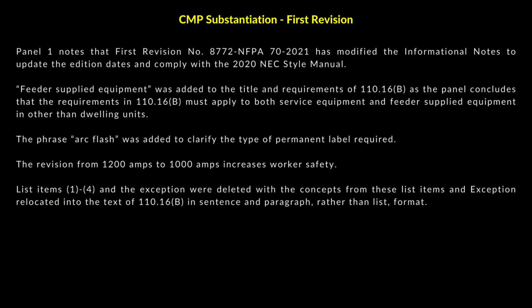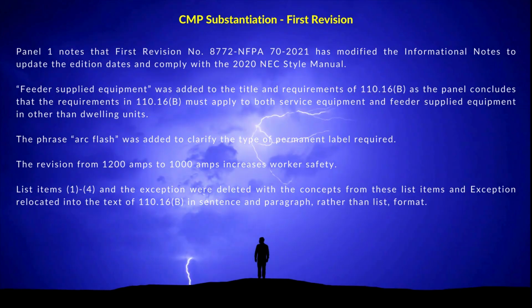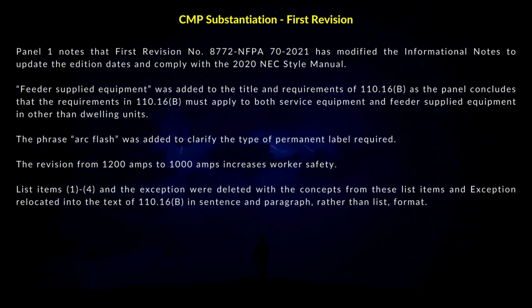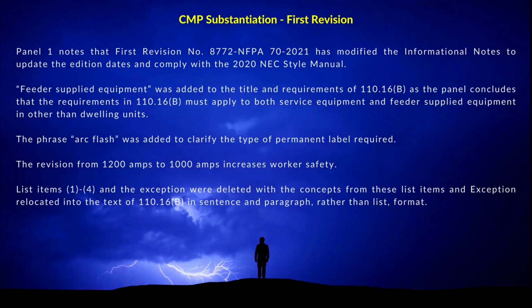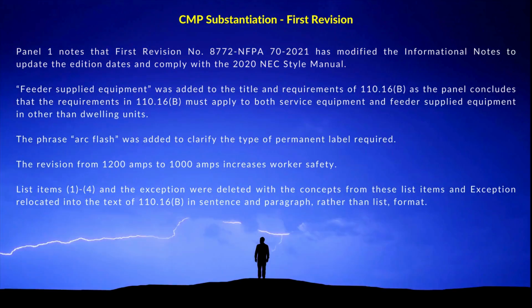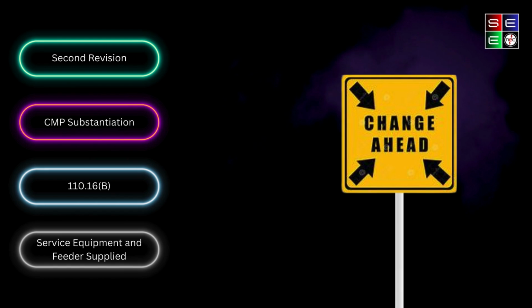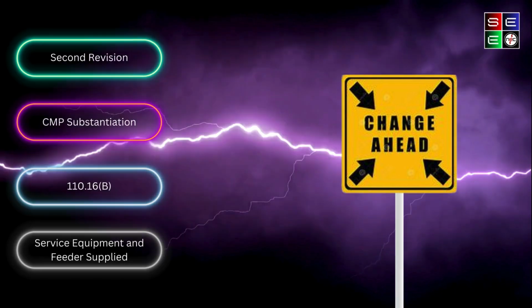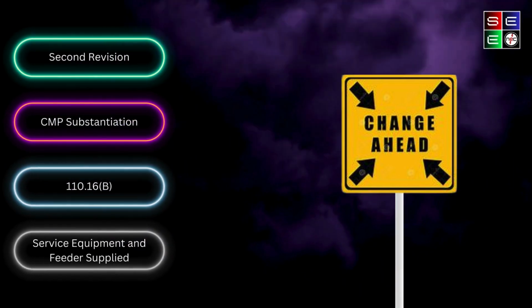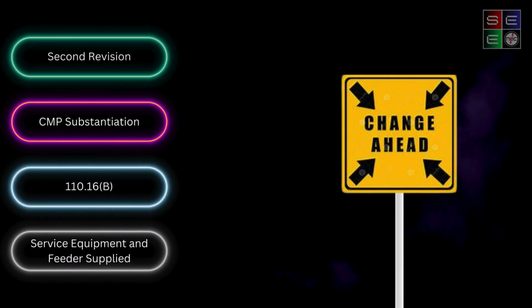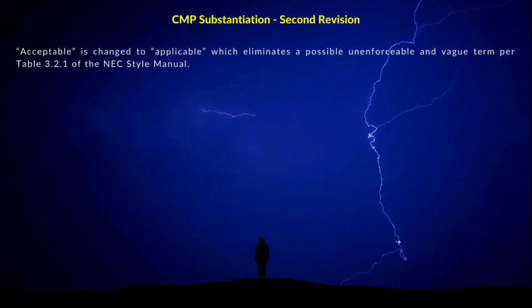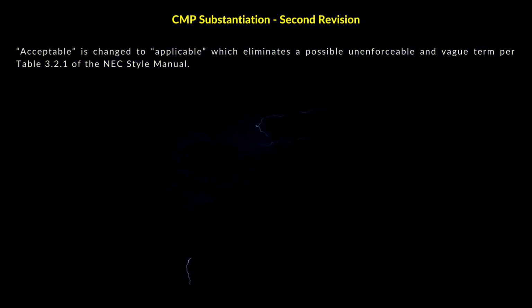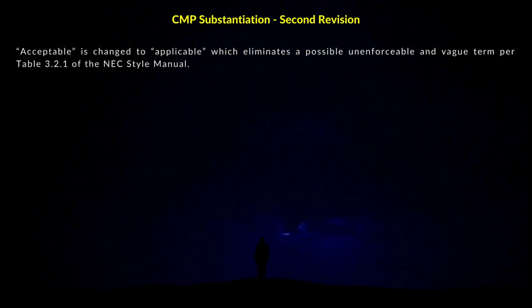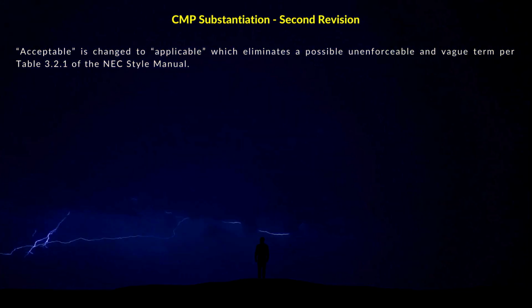List items 1 through 4 and the exception were deleted, with the concepts from these list items and exception relocated into the text of 110.16(B) in sentence and paragraph rather than list format. Acceptable is changed to applicable, which eliminates a possibly unenforceable and vague term per Table 3.2.1 of the NEC Style Manual.